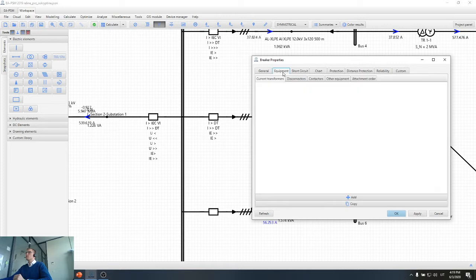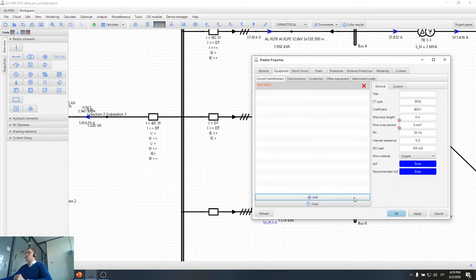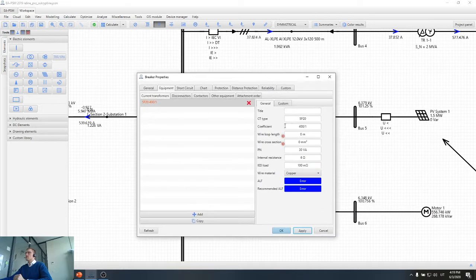So let's go to equipment, and in the first tab here we have current transformer selection capability. So I will add one current transformer to the network, and in order to select current transformer, actually we need to select the transformer transformation coefficient. Basically now the transformation coefficient is 400 amps. So we need to make sure that we know what is the wire length between the current transformer and the relay. So let's assume that wire length is 15 meters. Wire cross-section, let's say, is 2.5 millimeters square.